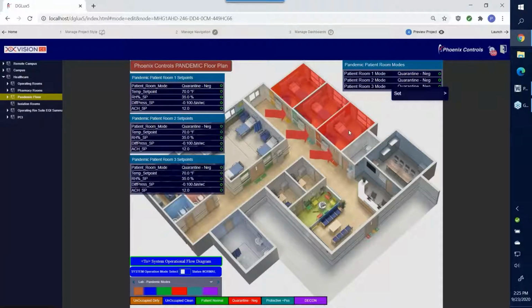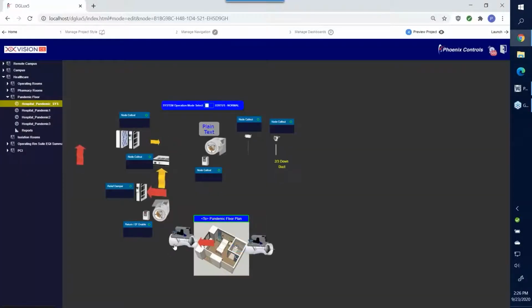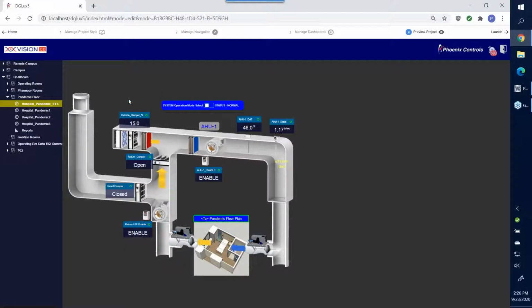All right, so all my rooms are now running negative. As you can tell, very high air change rates, ready to roll. But now we're going to go check on our air handling unit and see what's happening there. And so here we have a pandemic-ready air handling unit. As you can tell, we've got 15% outside air, relatively normal, and then just return air coming from these pandemic floors. With the switch of a button, we're going to increase our outside air up to 100%, shut off the return, and enable the exhaust fan. So now we have a fully pressurized suite. Now you have the dampers opening, the exhaust fan turned on, and your 100% outside air.